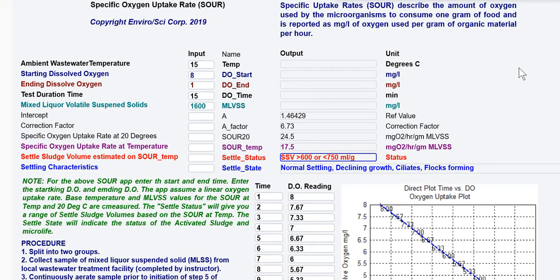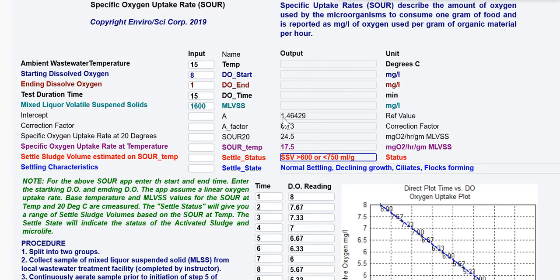The oxygen uptake rate is the amount of oxygen used or consumed per gram of food. The food is measured as volatile mixed liquor suspended solids. You have the ambient temperature of the wastewater, the starting dissolved oxygen of your test in a Winkler bottle, the ending dissolved oxygen value, the duration of the test, and the mixed liquor volatile suspended solids.